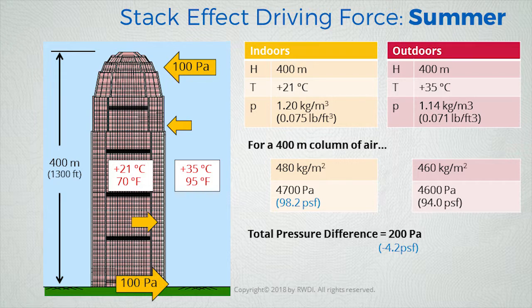This is an example where we start to see that in summer or warm climates, stack effect is not going to be as strong as in cold climates, and that's simply because the temperature difference is not as great. That said, summer stack effect can also be more difficult to control than winter stack effect, and I'll talk about that in a couple of minutes as well.